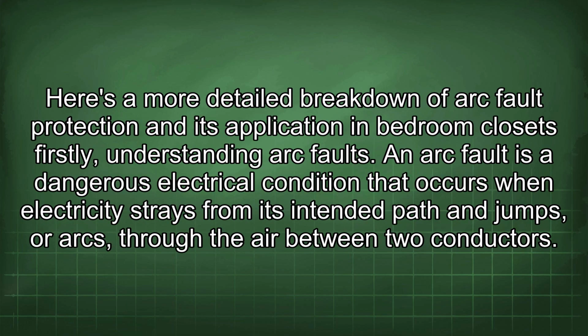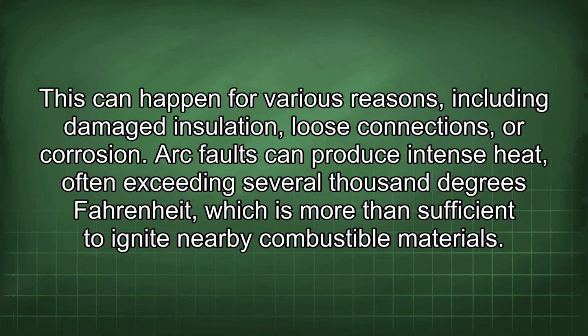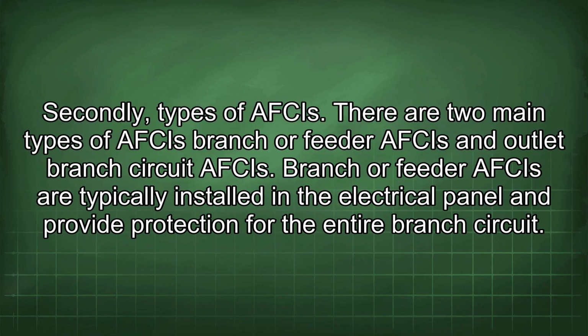Here's a more detailed breakdown of arc fault protection and its application in bedroom closets. Firstly, understanding arc faults. An arc fault is a dangerous electrical condition that occurs when electricity strays from its intended path and jumps, or arcs, through the air between two conductors. This can happen for various reasons, including damaged insulation, loose connections, or corrosion. Arc faults can produce intense heat, often exceeding several thousand degrees Fahrenheit, which is more than sufficient to ignite nearby combustible materials. Secondly, types of AFCIs.